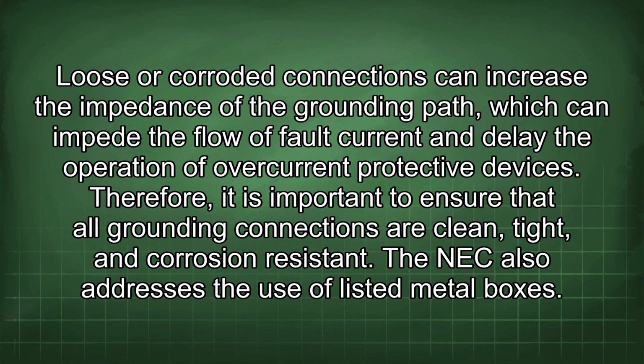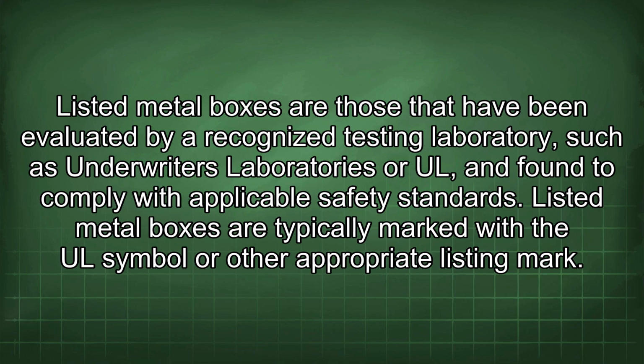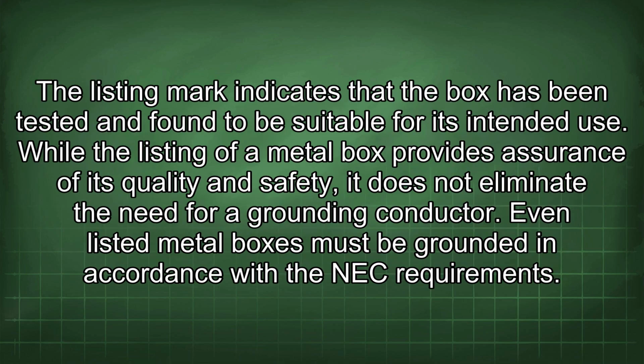The NEC also addresses the use of listed metal boxes. Listed metal boxes are those that have been evaluated by a recognized testing laboratory, such as Underwriters Laboratories or UL, and found to comply with applicable safety standards. Listed metal boxes are typically marked with the UL symbol or other appropriate listing mark. The listing mark indicates that the box has been tested and found to be suitable for its intended use. While the listing of a metal box provides assurance of its quality and safety, it does not eliminate the need for a grounding conductor. Even listed metal boxes must be grounded in accordance with the NEC requirements.